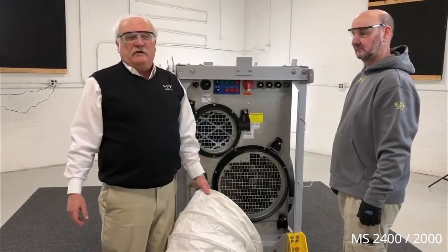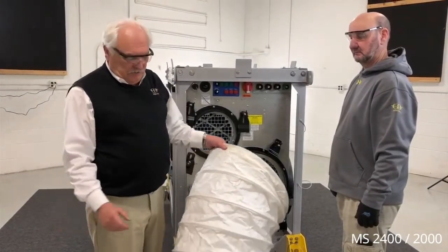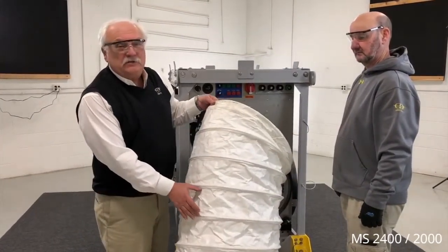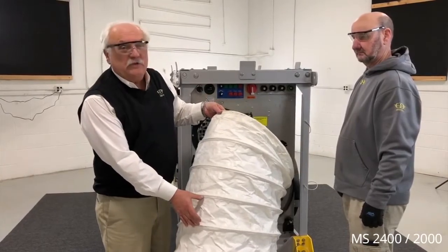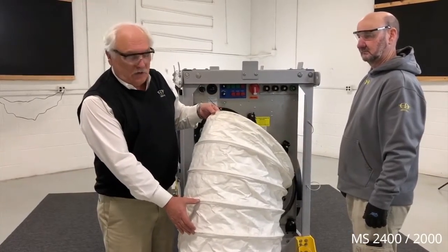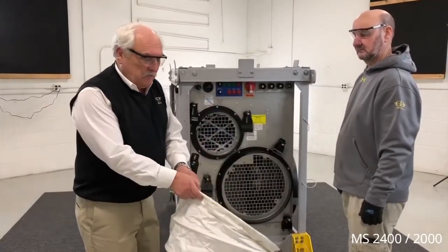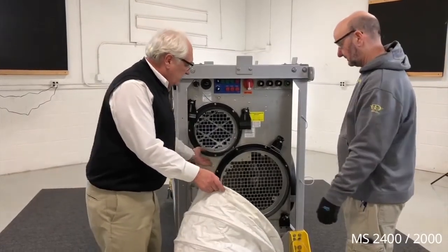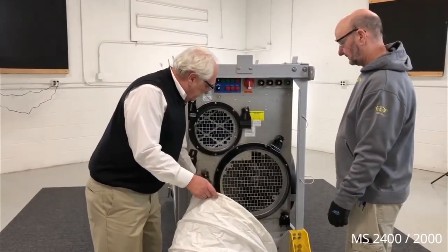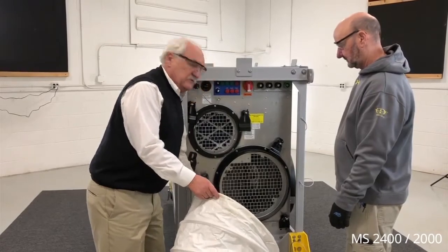For the supply air outlet, which is a positive airstream, we recommend 6-inch pitch ducting, 6 inches between the reinforcing ribs on the ductwork. We take the 20-inch ductwork and connect it to the unit using the 4 quick connect clamps.